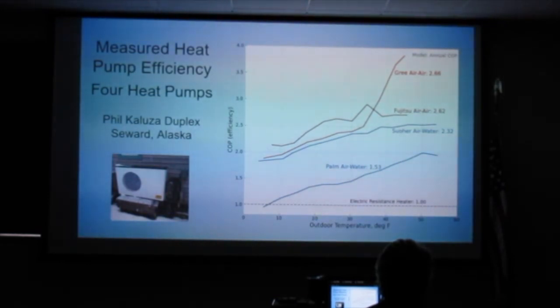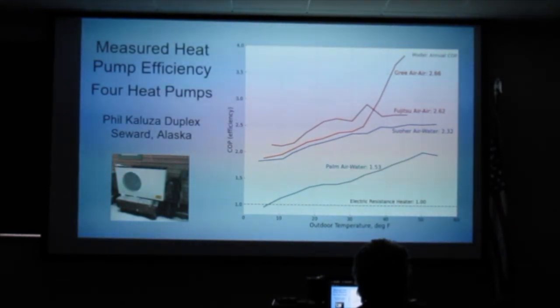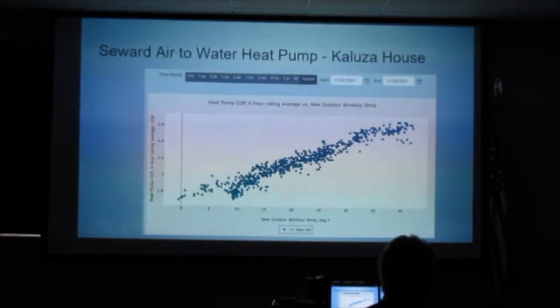So you have to be able to accurately measure the temperature across that face, and accurately measure the flow of air coming out of those things. It turns out it's very complicated. I cheated on my little apartment. I had it vacant in the winter, so I was able to shut off the heat pump, run straight electricity which I knew the efficiency of, then turn on the heat pump for a day or two, then go back to straight electric. We did that over the course of a winter and could come up with a pretty good, accurate number.